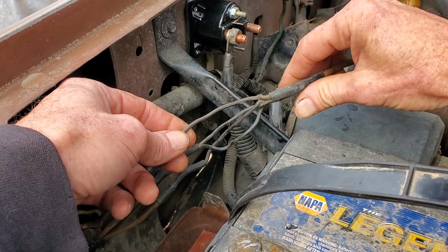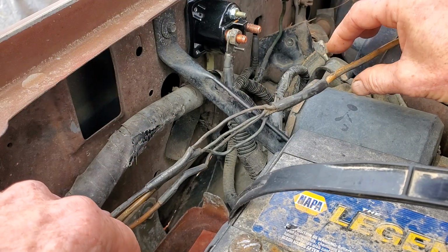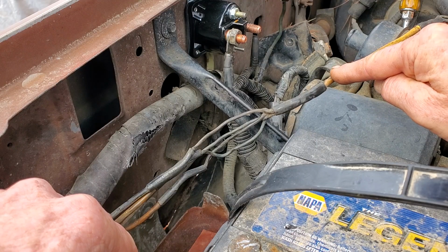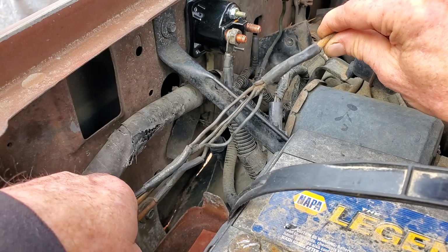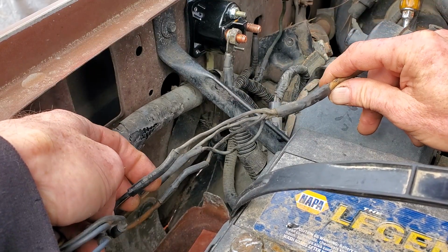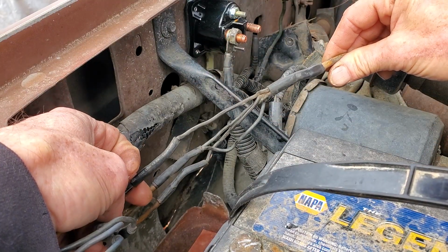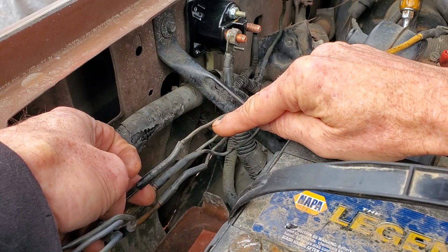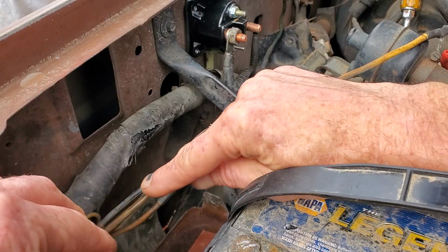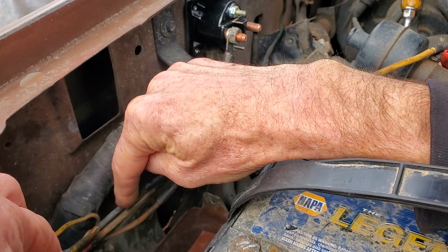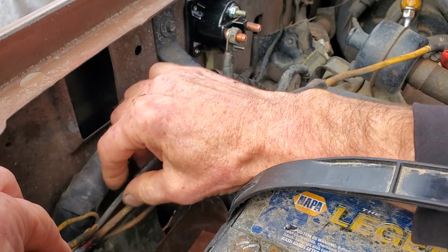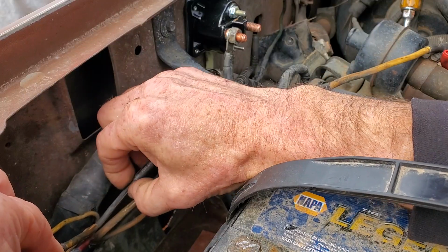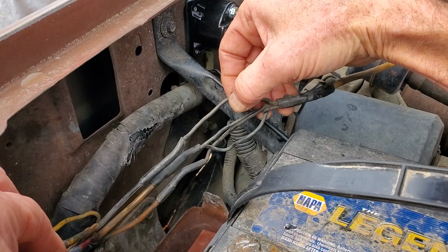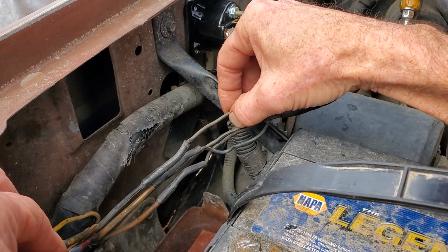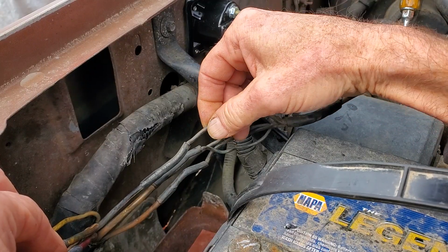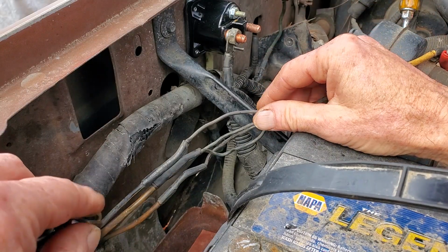It's a special insulation. Secondarily, another thing about fuse links is you've usually got a wire that's a big gauge on one side and a big gauge on the other end for this particular fuse link. But the fuse link will be like 3 or 4 times smaller in wire gauge than the circuit that it feeds. Notice that's a black and yellow wire tapped into, I would say this is like a number 10 gauge right here. But it's interrupted by a fuse link that's almost 18 gauge right there. It doesn't make logical sense in the world of electricity, but it is what it is.